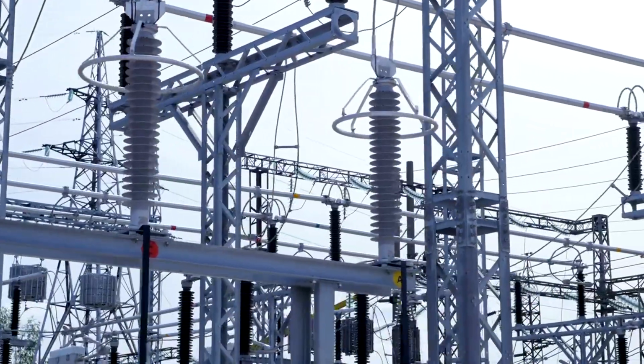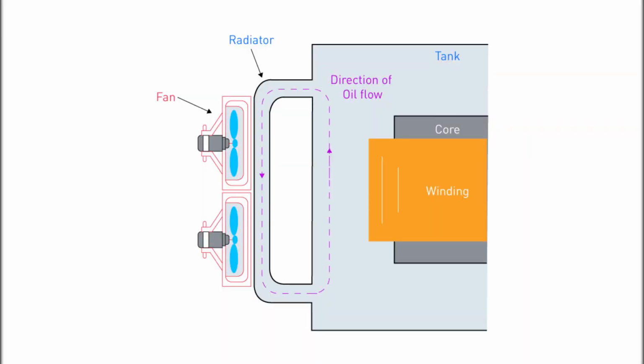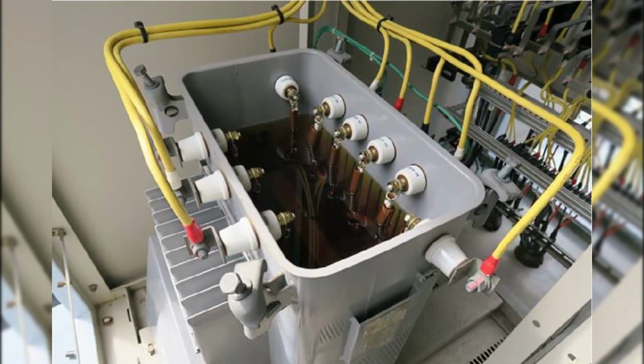Heat management is another major challenge. Whenever electric current flows through the copper windings, a small amount of electrical energy is converted into heat due to resistance. Small transformers are usually cooled by natural airflow or fans, while the enormous transformers used in electrical substations are commonly immersed in special insulating mineral oil. This oil serves two important purposes: it removes heat from the windings and provides excellent electrical insulation.